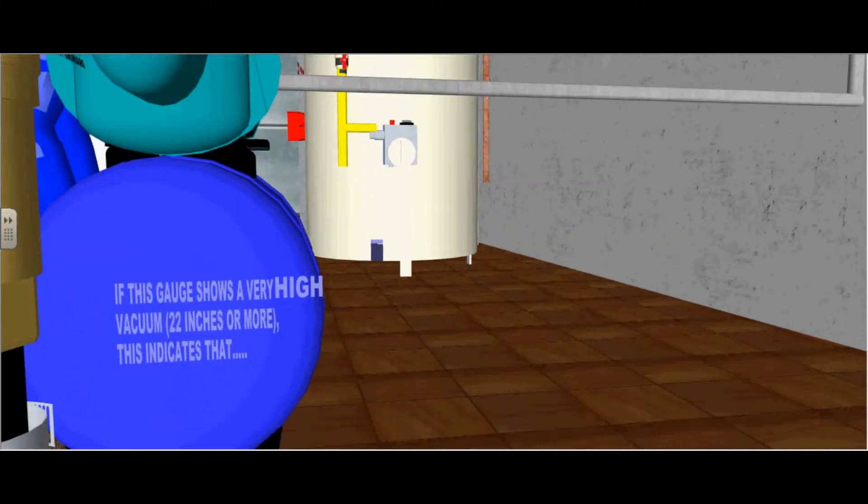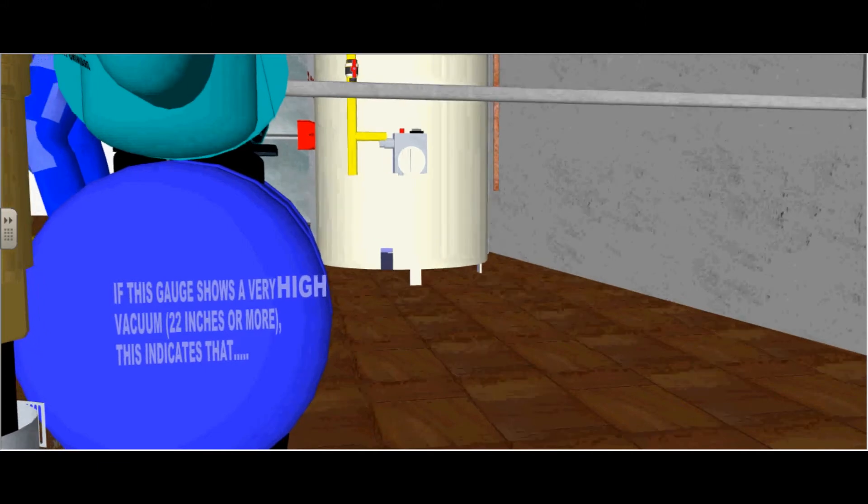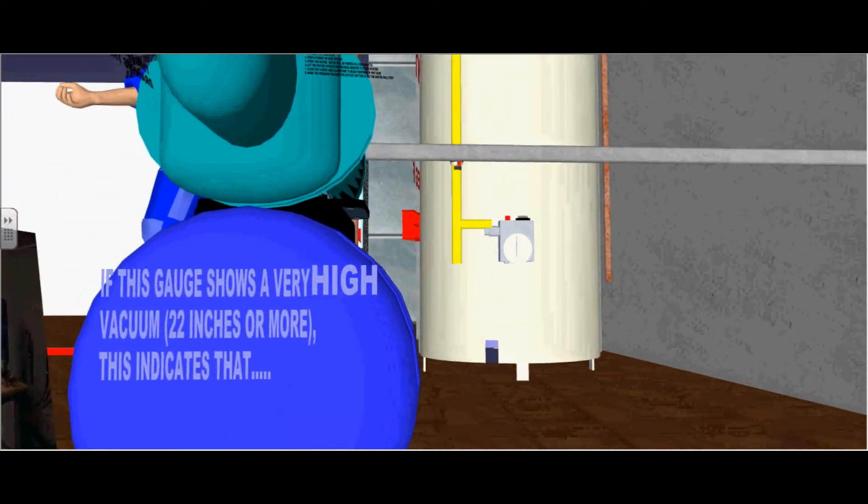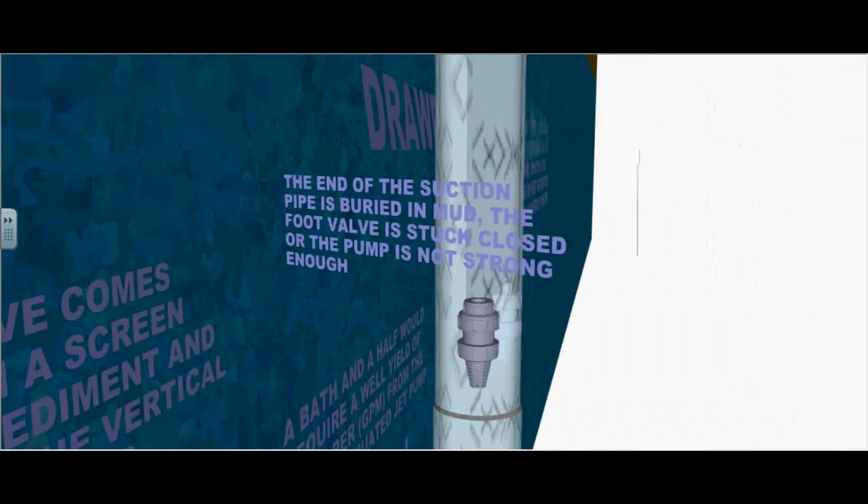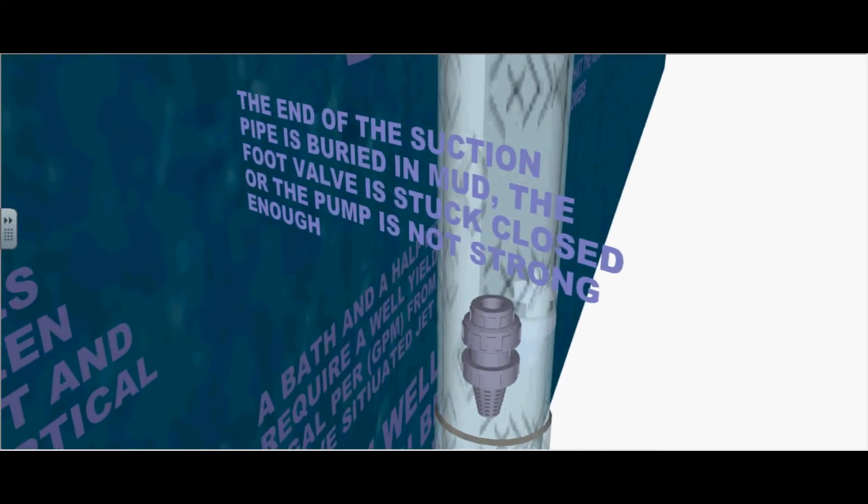If this gauge shows a very high vacuum of 22 inches or more, this will then indicate that the end of the suction pipe is buried in mud, the foot valve is stuck closed, or the pump is not strong enough.